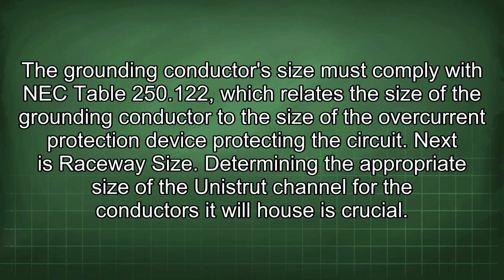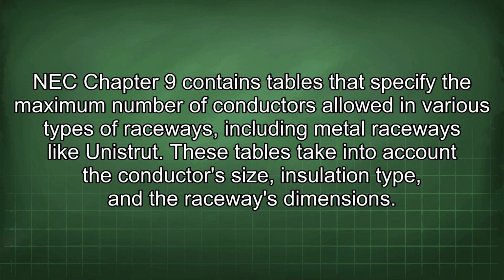The grounding conductor size must comply with NEC Table 250.122, which relates the size of the grounding conductor to the size of the overcurrent protection device protecting the circuit. Next is raceway size. Determining the appropriate size of the Unistrut channel for the conductors it will house is crucial. NEC Chapter 9 contains tables that specify the maximum number of conductors allowed in various types of raceways, including metal raceways like Unistrut. These tables take into account the conductor size, insulation type, and the raceway's dimensions.